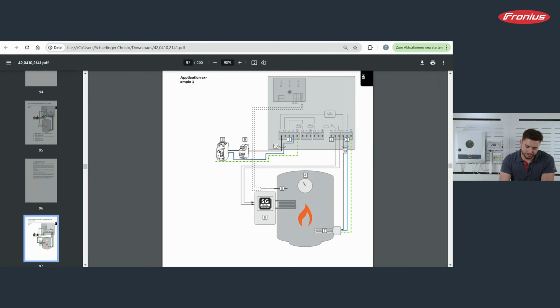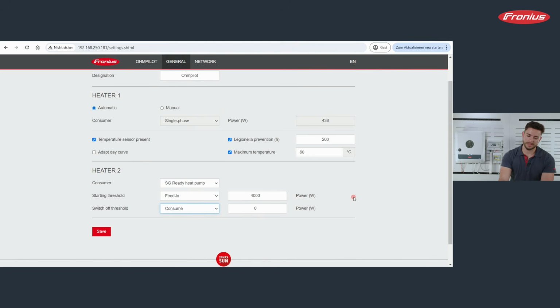And the main benefit now, I quickly switch back to our overview. The main benefit of connecting a Smart Grid Ready heat pump and a heating rod in one system with the Ohmpilot is that up to the threshold where we want to switch on the Smart Grid Ready heat pump, we use this surplus power, as mentioned before, dynamically with our single phase connected heating rod. So both benefits at the same time. Up to the 4 kilowatt, we use the single phase dynamically controlled, and from 4 kilowatt and above, we use the highest efficiency with our Smart Grid Ready heat pump. So this is again one way to use the multifunctional relay within our Ohmpilot.